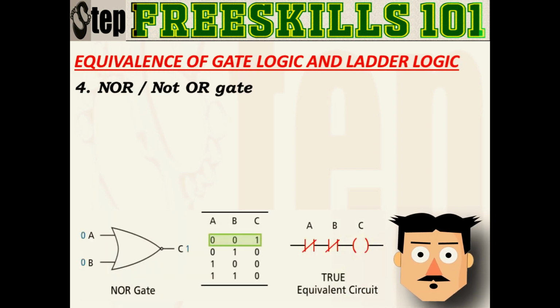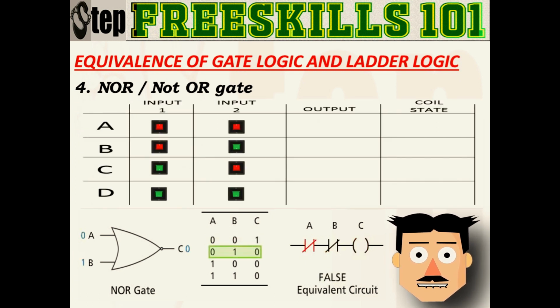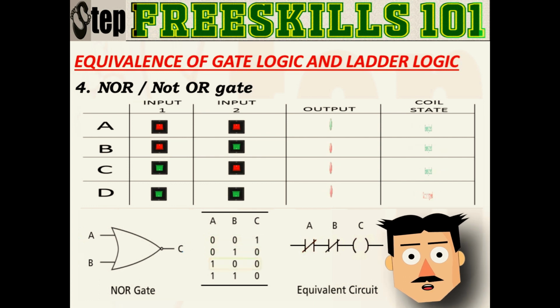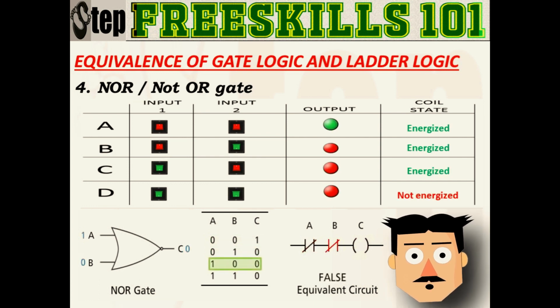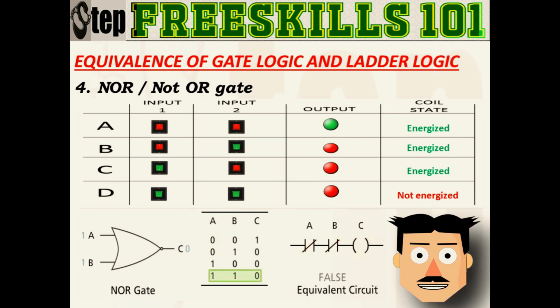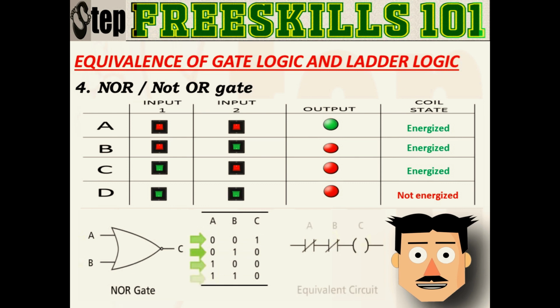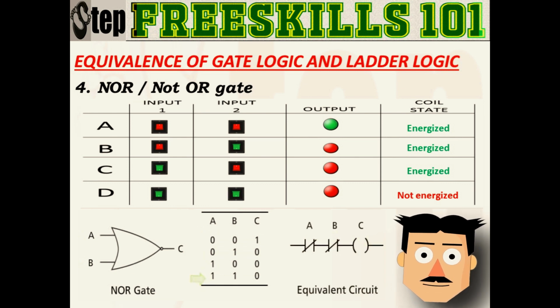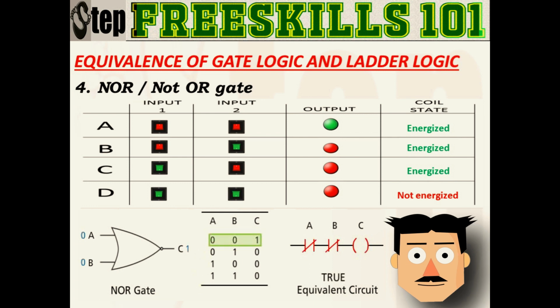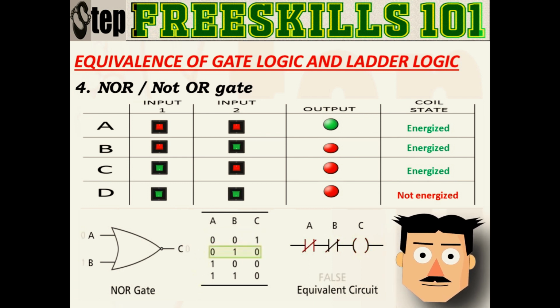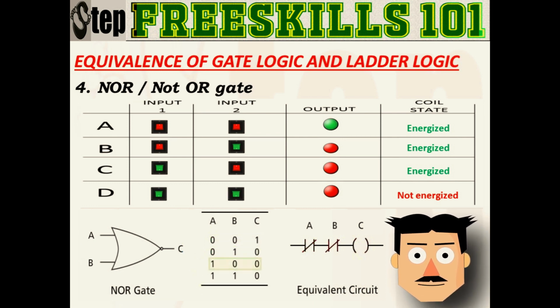Four, NOR, not OR gate. Opposite of the OR gate, and its ladder logic is like an AND gate, but with normally closed contacts. If either one or both of them are true, then the output will be in the off and false state. An example application is when you want to stop the motor: either the emergency button or the stop button is pressed.